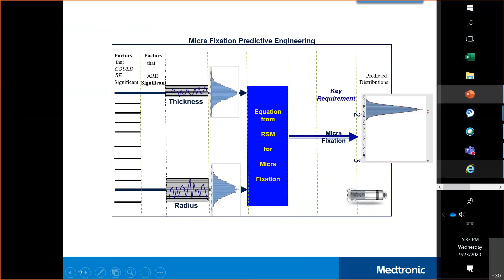Well, anyway, we brought that in there, and we now modeled it. What turns that equation from a deterministic model into a probabilistic one is allowing for the manufacturing variation on the thickness and on the radius. What we found, using Monte Carlo simulation, is that a high percentage of the time it would be below 2 newtons and we'd have a failure. So we found a way to optimize the thickness and radius of this design, shown here, so that we get really good capability, well within the spec limits of 2 to 3 newtons, when we put this into production. So we did that to optimize Micra fixation. We did similar things for that longevity that I mentioned before.